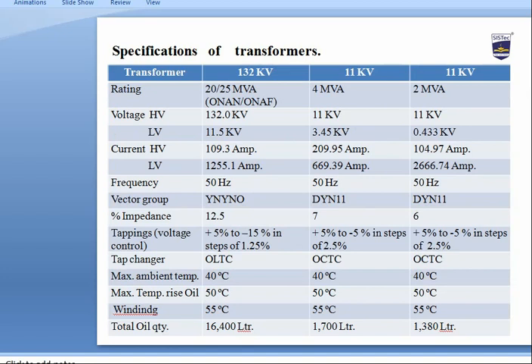Transformer specifications include: rating, high voltage winding and low voltage winding levels, current for HV and LV, frequency (50 Hz in India), vector group, percentage impedance, tap changer type (offline or online), maximum ambient temperature, maximum temperature rise of oil, winding temperature, and total oil quantity.